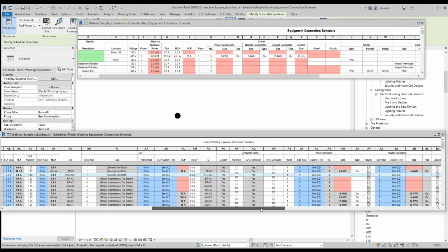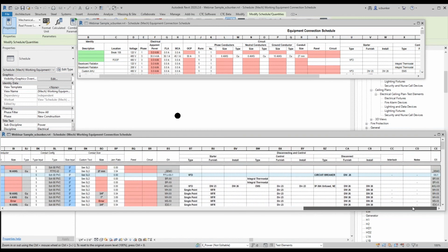Some things it doesn't do: voltage drop. It doesn't do correction factors, like for more than 3 current carrying conductors or for different ambient temperatures. It does do jam ratio. So if it calculates the jam ratio and finds that it is in the problematic range, it automatically increases the conduit up 1 size. And it reports the final jam ratio to you too, over here.